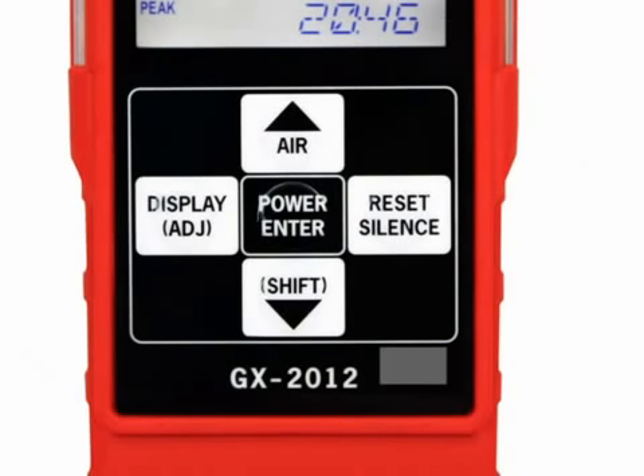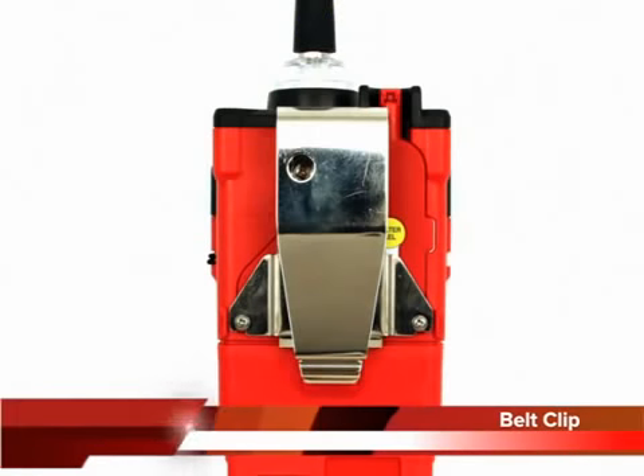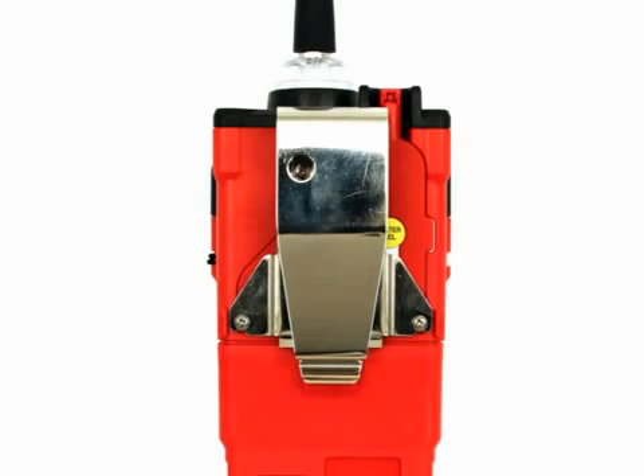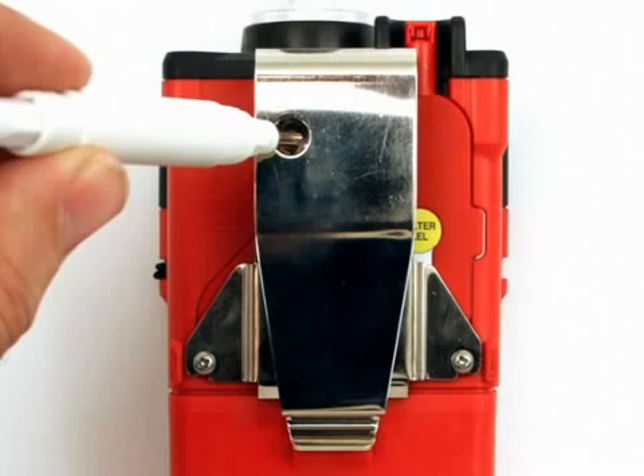There is an infrared communication port located just below the reset silence button, which is used to transfer information when the instrument is used with one of the calibration stations or downloading accessories. The belt clip is used to easily clip the GX 2012 on a belt. There are 3 threaded inserts on the back of the case. These are used to mount the belt clip. 2 of the inserts are also for the flow chamber.